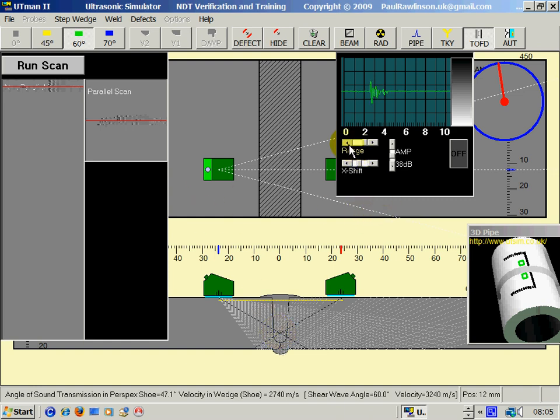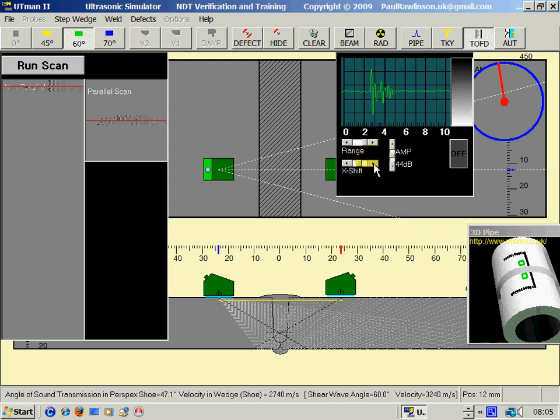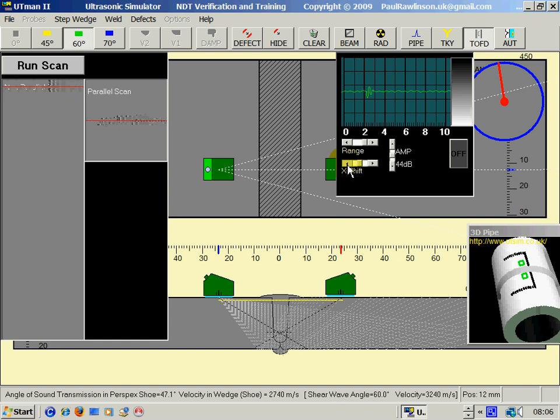We've got our range control and our amplitude. Now the first thing to do is find the initial pulse. Find the lateral wave. There it is there. Squash the range up so we can see the back wall.